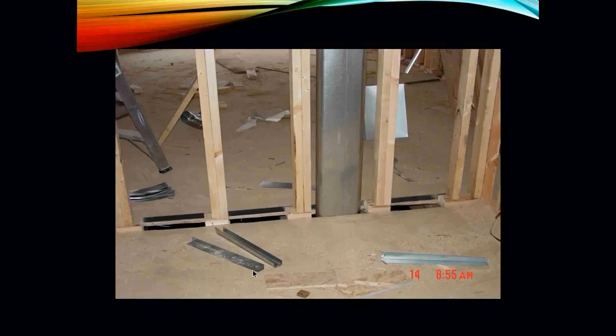Here's another good picture of what we're talking about. It's open, so once this piece is put in, our sheet metal protectors would get installed here, and then we'd fire caulk all the way around. Another good practice is right where this seam is, we'd take some mastic and seal this fitting together, and once that mastic dries, hit it with a piece of silver tape so it'll be leak free.